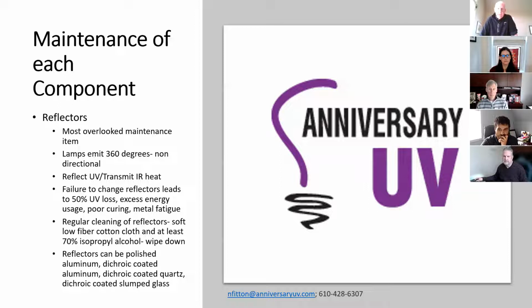And eventually you're going to have metal fatigue, because in addition to reflecting UV light, the reflector laying flat against the extrusion behind the lamp actually transmits the infrared heat to the extrusion and away from the lamp substrate. Part of your regular cleaning has to be wiping down the reflectors weekly or bi-weekly, with a soft, low fiber cotton cloth and at least 70% isopropyl alcohol. You want to wipe these down because they attract external contaminants. Once those contaminants get baked on, you're not going to get them off. And once they're baked on, you are not getting reflectivity and you're not getting heat transmission.